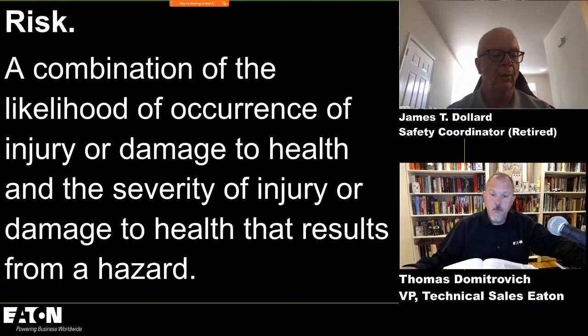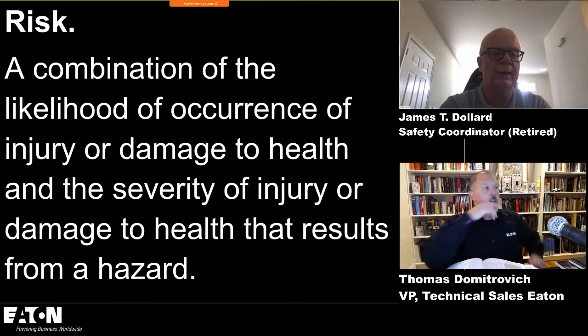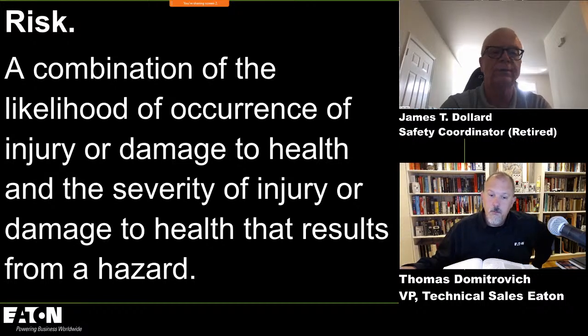So really what we're talking about today is a hazard, right? And 70E defines a hazard as a source of possible injury or damage to health. So when a hazard like a shock hazard or an arc flash hazard exists, then it's there. We don't do a risk analysis. NFPA 70E used to call it a hazard risk analysis. We don't do a risk analysis of the hazard. The hazard is there. So we qualify the hazard. We understand what it is.